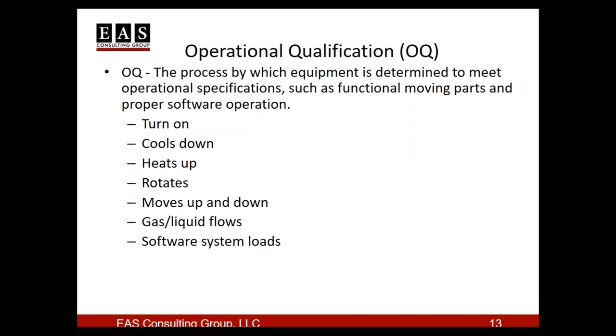Operational qualification is making sure that the piece of instrumentation or equipment actually operates. This is simple stuff: making sure it turns on, if it's supposed to cool down it does that, if it's supposed to heat up it does that, if it's supposed to rotate it does that. If there's electronic equipment that's supposed to move it up and down, if you've got gases, the gases are flowing, and if there's software associated, the software is appropriate and everything works.